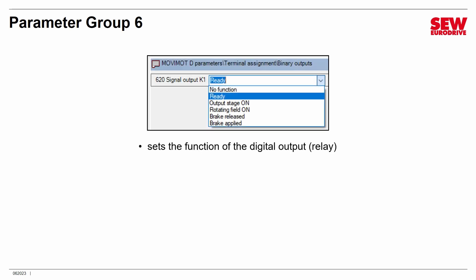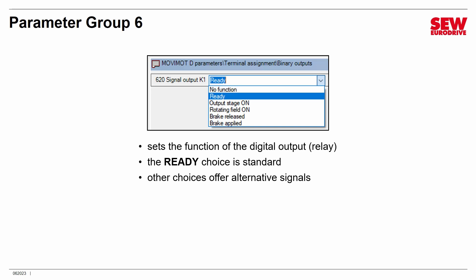There's also something handy in Parameter Group 6 — you can assign the function of the digital output, the relay contact. By default it's assigned to the ready signal indicating if the Movimot is ready to run. But you can assign it to other things: output stage on (output transistors activated), rotating field on (motor starting to turn), brake released (brake allowed motor to turn), or brake applied (brake closing to stop motor). You can assign any of these to the relay, and if that signal is true the relay will close. Alternatively, assign it to no function.